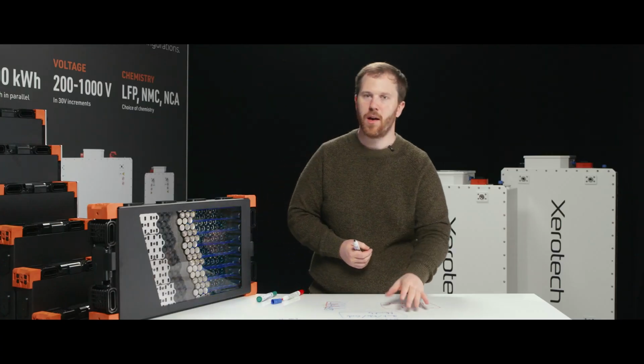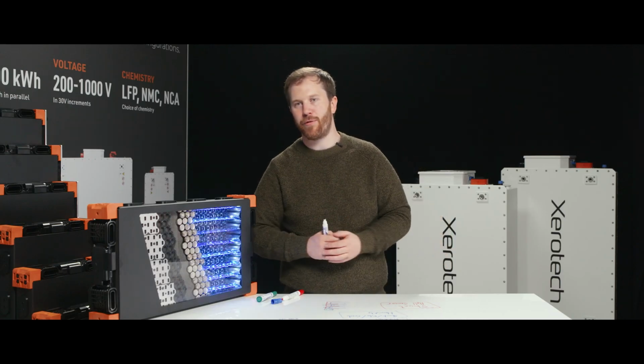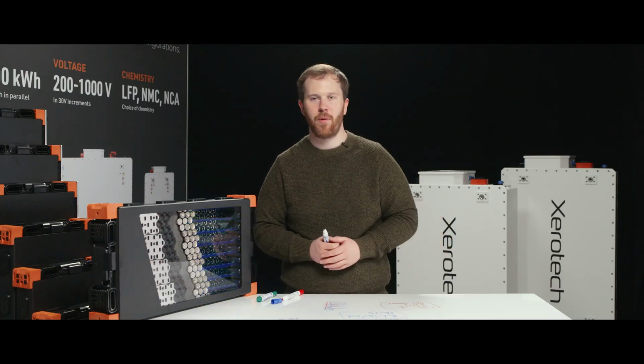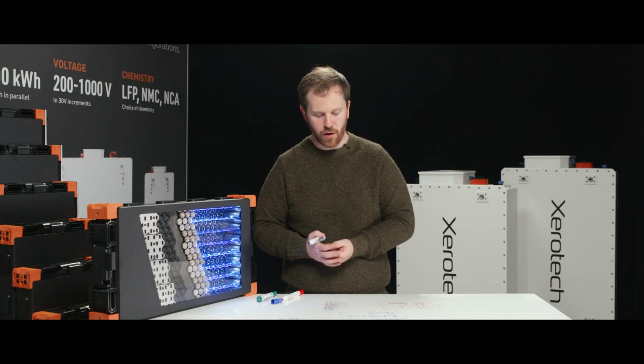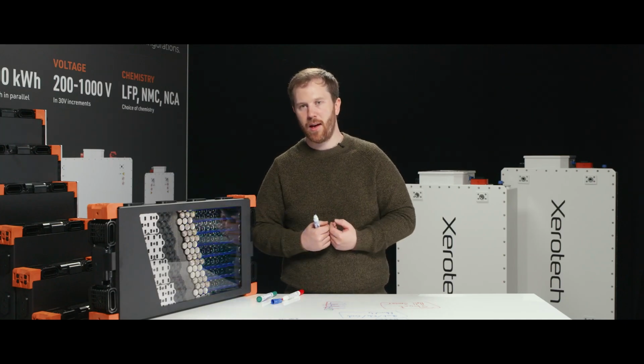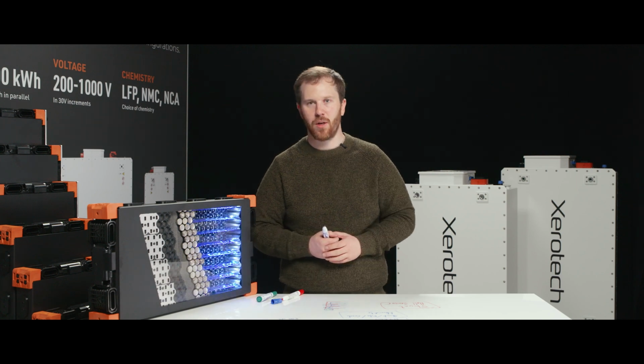Now, the other safety mechanisms that are within batteries in terms of active measurement, active protection systems, it varies from supplier to supplier. Some employ accelerometers that are looking at shock, vibration. These can be set at a threshold, so you can set a crash limit. If you see a G shock above a certain threshold, you say, looks like a crash. I'm going to open contactors. I'm going to blow the pyro fuse, whatever you might do. Or you might be looking at humidity and temperature at a system level and many other factors. It depends, but your core safety elements are voltage, temperature, current, and then looking at main breaks in isolation or breaking power conductors under load.